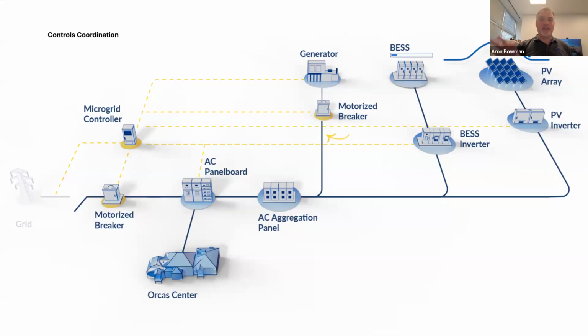People ask us all the time, how do you manage the generator? Well, what we do is we use the rest of the system to keep the generator happy. We know from our controls what the optimal run rate is for that generator, and so we run that generator at its happy place all the time, to use a little Adam Sandler. We keep it in its happy place. And then we are able to respond very rapidly with the battery energy storage system to what the generator needs. So if the loads spike, generators a lot of times don't like to see a lot of transient loads. So we can smooth those transient load spikes with the battery energy storage system.